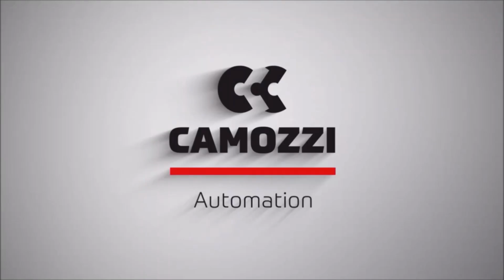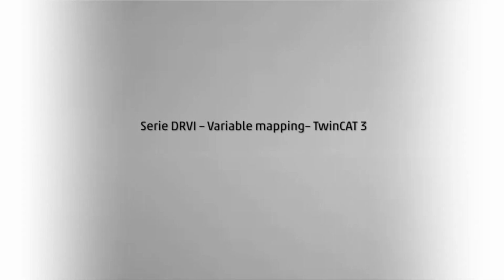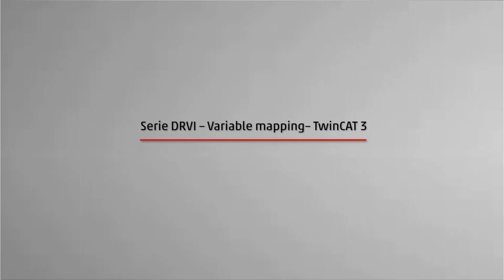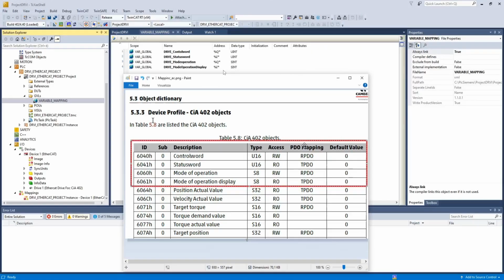In this tutorial we will see how to correctly map some variables of the cyclic communication of the Camozzi device on Ethercat bus. For the tutorial, as an example, only the first two input variables and the first two output variables of those available on the Camozzi DRVI for cyclic communication have been mapped.